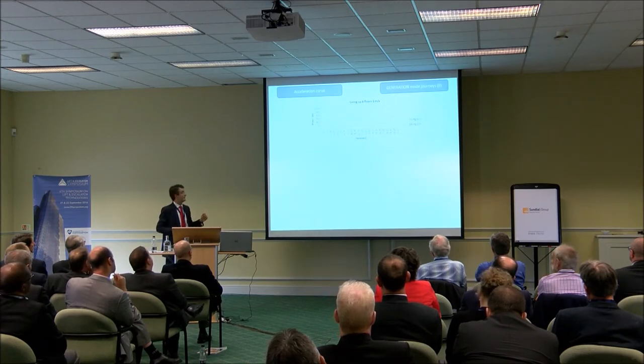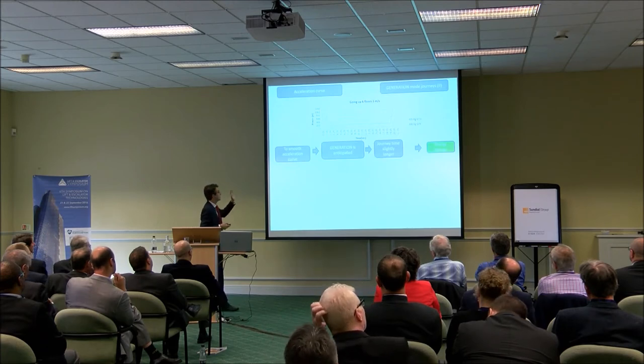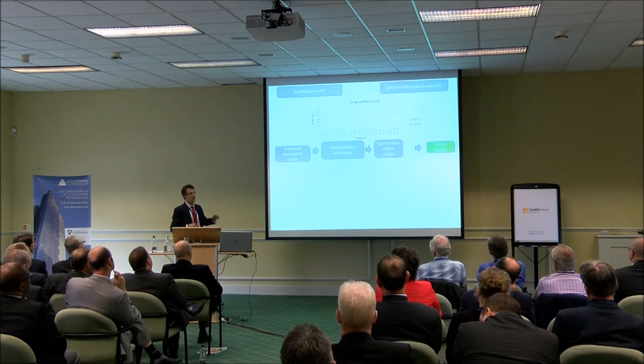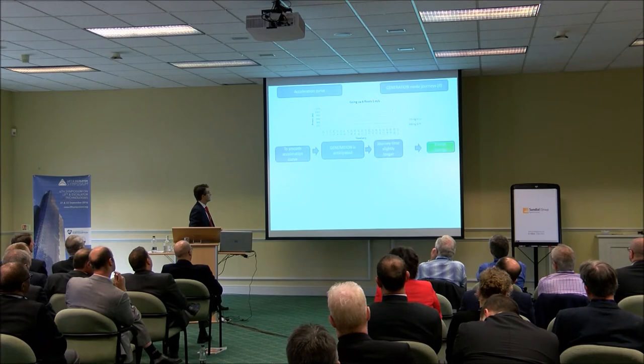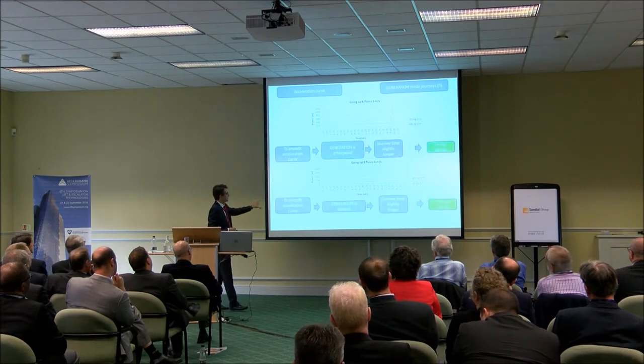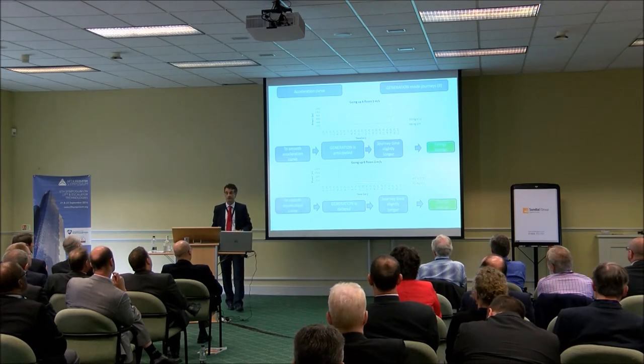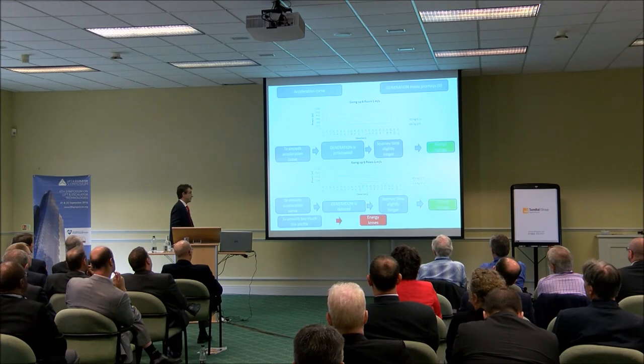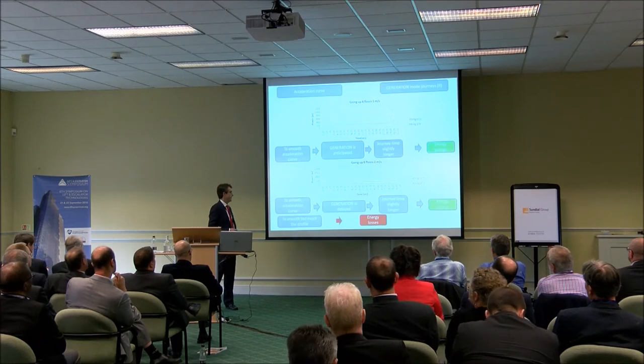If we increase the load a little more, we are still in generation mode. Here we suggest doing the opposite — smoothing the acceleration profile — and we can see how generation is anticipated. Journey time is slightly longer, about half a second, and we find energy savings. If we add more load and smooth the acceleration curve again, generation is not anticipated but delayed. However, it is still interesting for energy savings. Of course, if we smooth the acceleration profile too much, we will reach a point where energy losses appear.